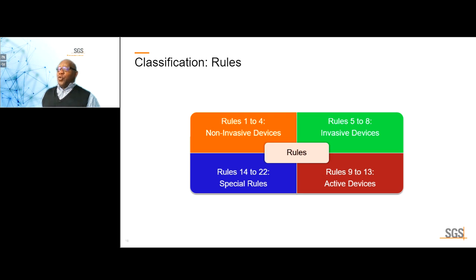There are a total of 22 classification rules. Again, going clockwise, rules 1 to 4 are applicable to non-invasive devices. Rules 5 to 8 are applicable to invasive devices. Rules 9 to 13 are applicable to active devices, devices that have energy. And then rules 14 to 22 are so-called special rules. So for devices that utilize animal tissue, devices that incorporate a medicinal substance, devices that have nanomaterials, substances, etc.